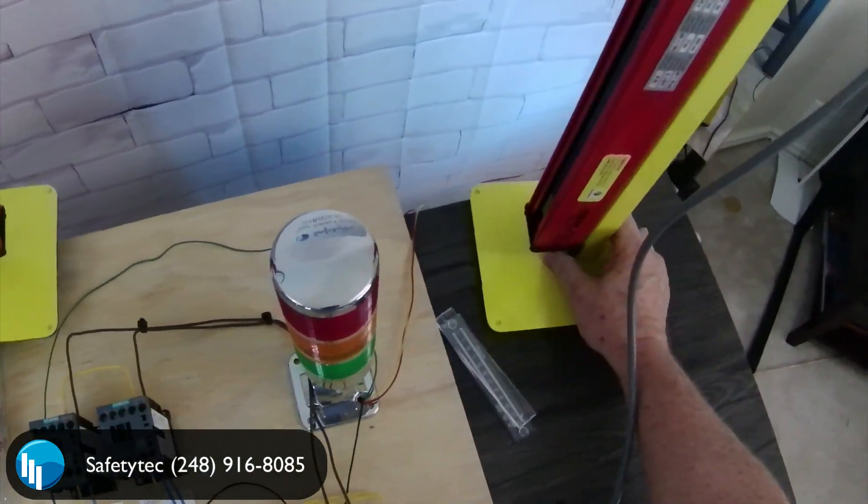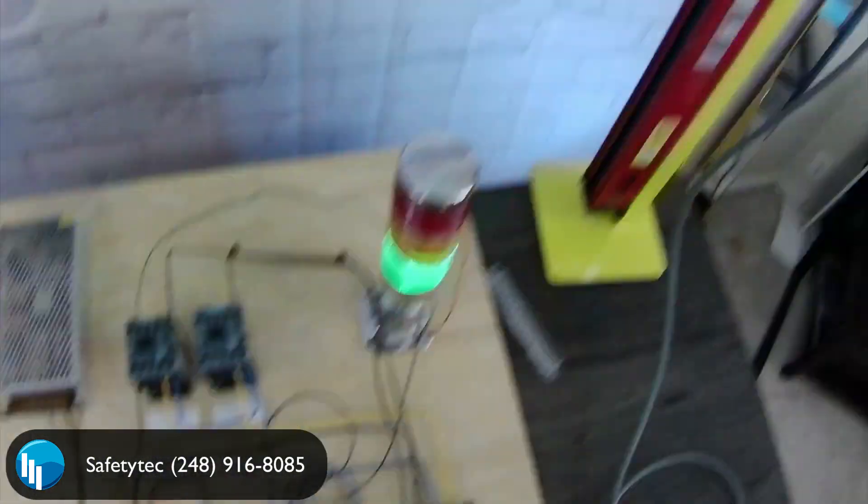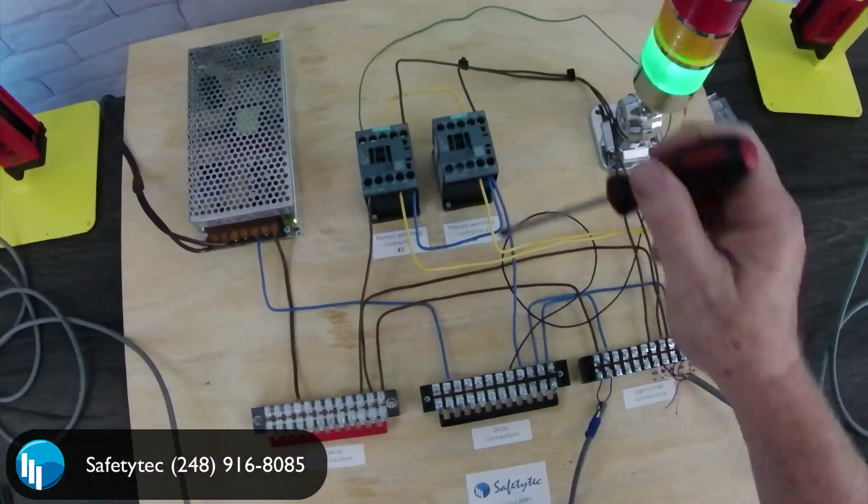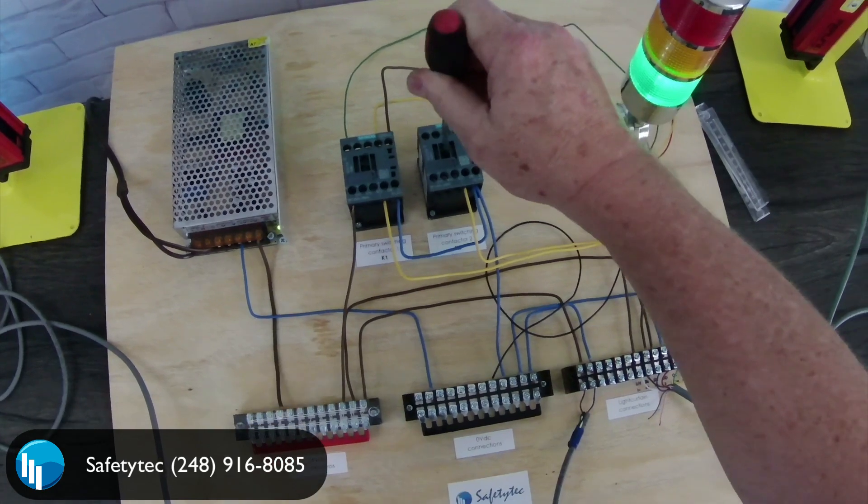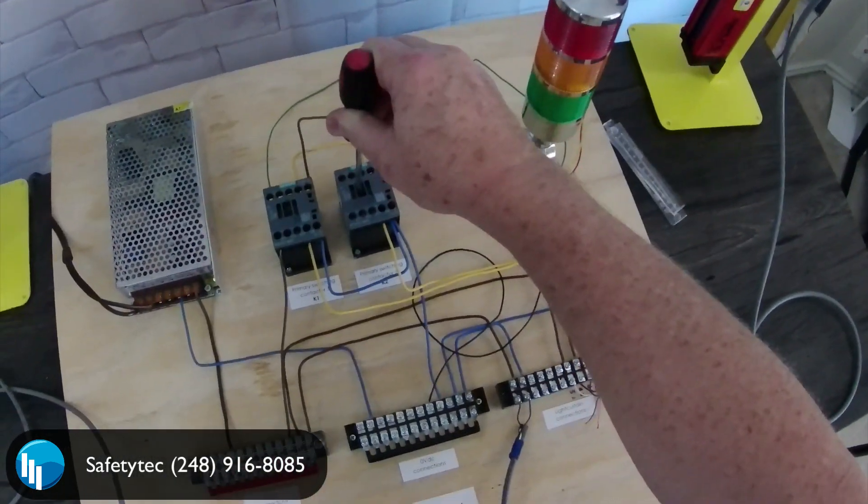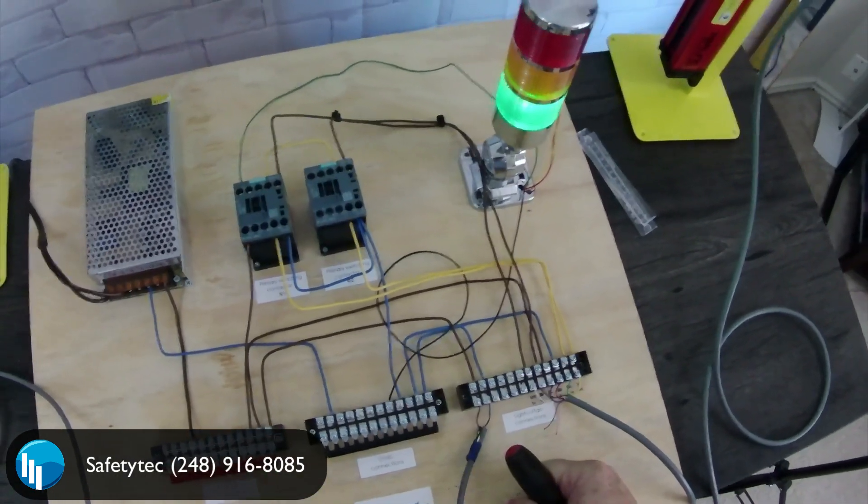I think there's lights in the way. There you are. System functioning. And to show you the EDM circuit is working, if I jam this contactor in place, you can see it doesn't work. The light curtain has detected that this contactor has failed and won't start the machine until it's fixed.